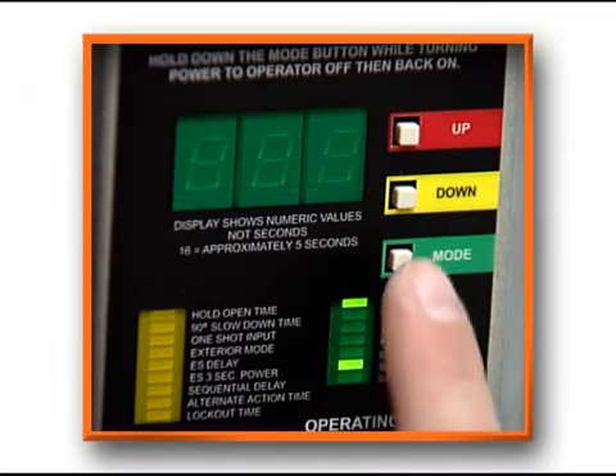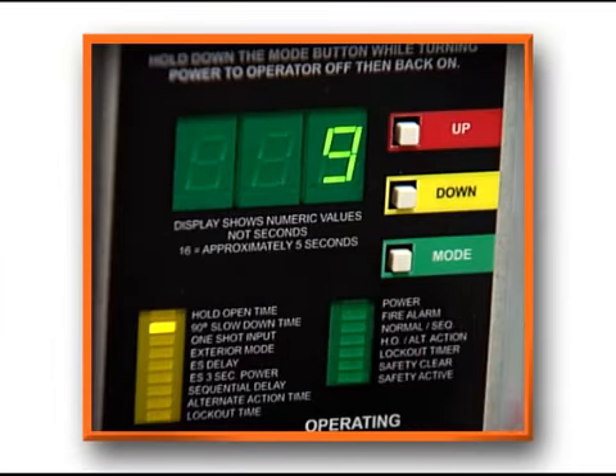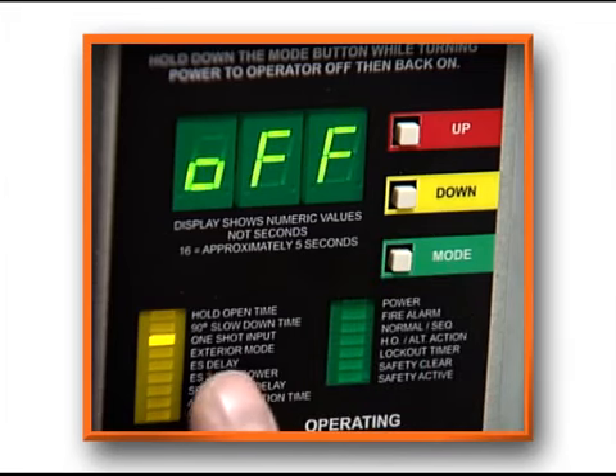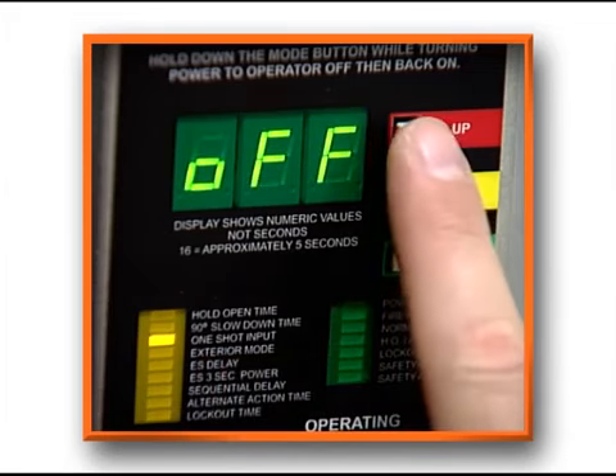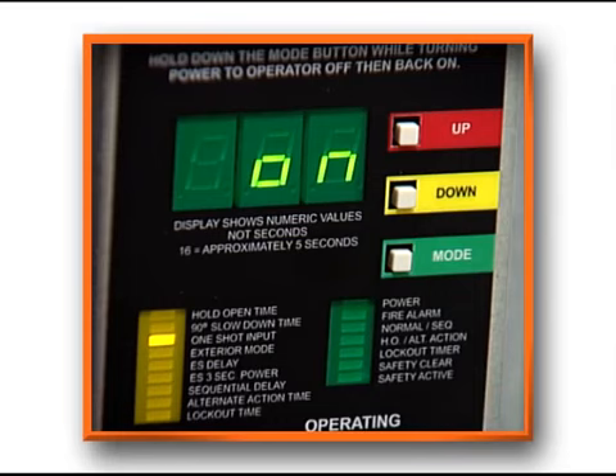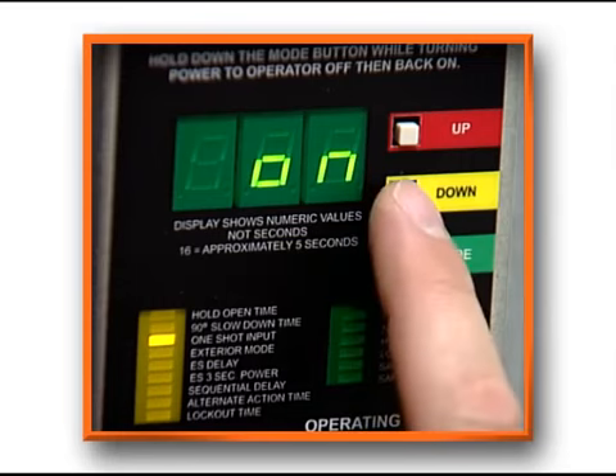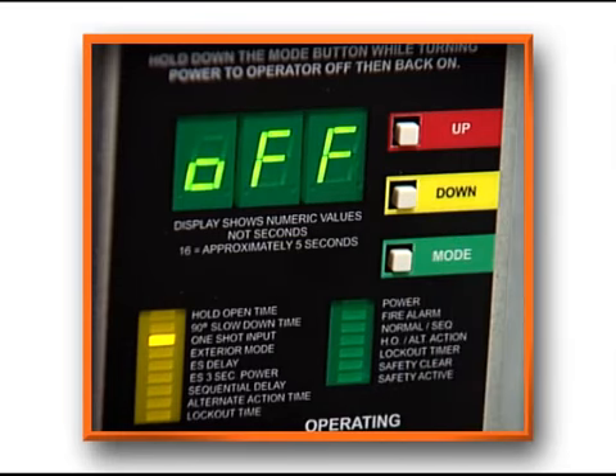The one-shot input mode is an on or off option. If switched off, the hold open delay starts at the last activation input signal. If switched on, the hold open delay starts at the first activation input signal and ignores other activation inputs. The default is off.